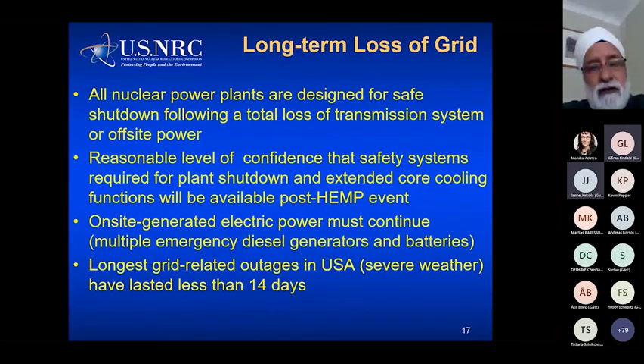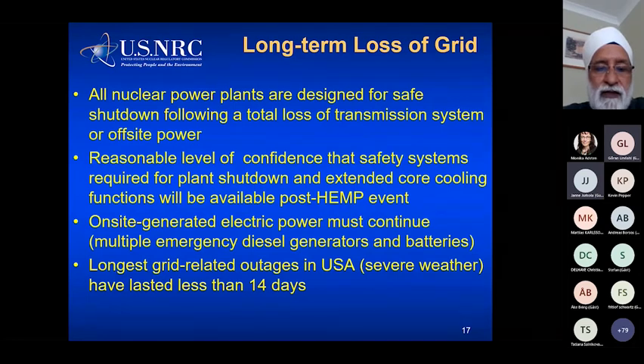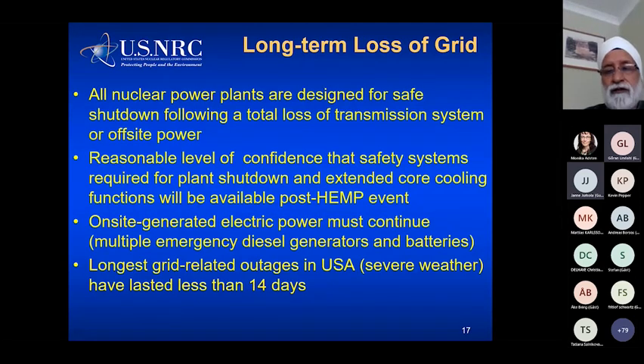So we know that all nuclear power plants are designed for safe shutdown following a total loss of transmission system or offsite power. Like I said, we have a reasonable level of confidence that safety systems required for plant shutdown and extended core cooling functions will be available post EMP event. We know we need to have the emergency diesel generators available. They must continue to function. And what we also know from our past operating experience is that the maximum outage we've suffered in the US is about 14 days of loss of offsite power. In the case of EMP, it could be longer. So we need to evaluate long-term core cooling functions.